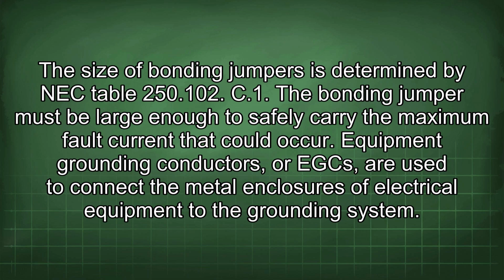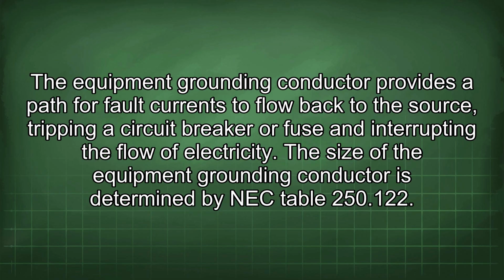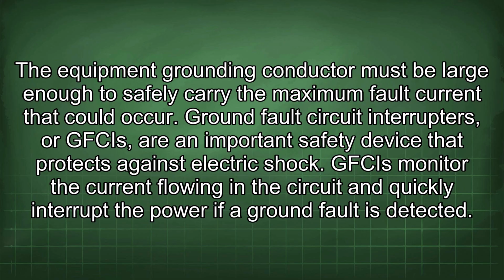Equipment grounding conductors, or EGCs, are used to connect the metal enclosures of electrical equipment to the grounding system. The equipment grounding conductor provides a path for fault currents to flow back to the source, tripping a circuit breaker or fuse and interrupting the flow of electricity. The size of the equipment grounding conductor is determined by NEC Table 250.122. The equipment grounding conductor must be large enough to safely carry the maximum fault current that could occur.